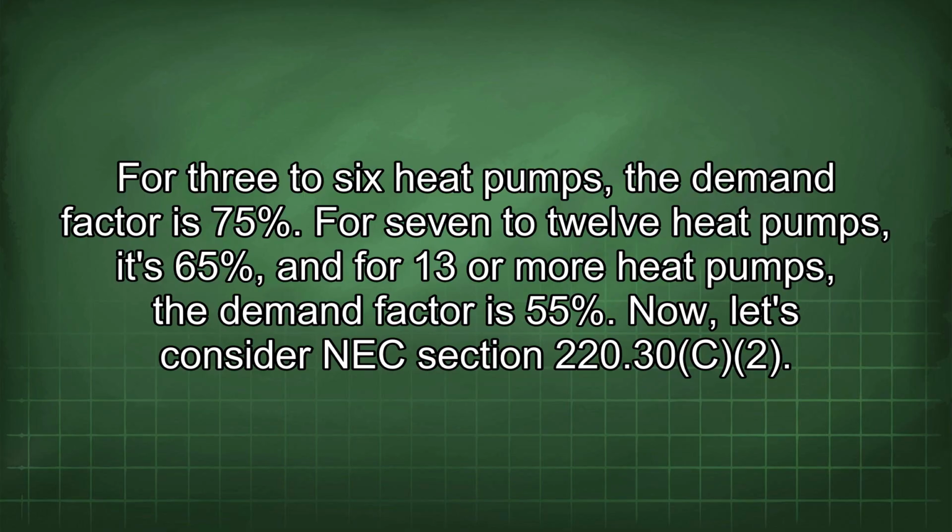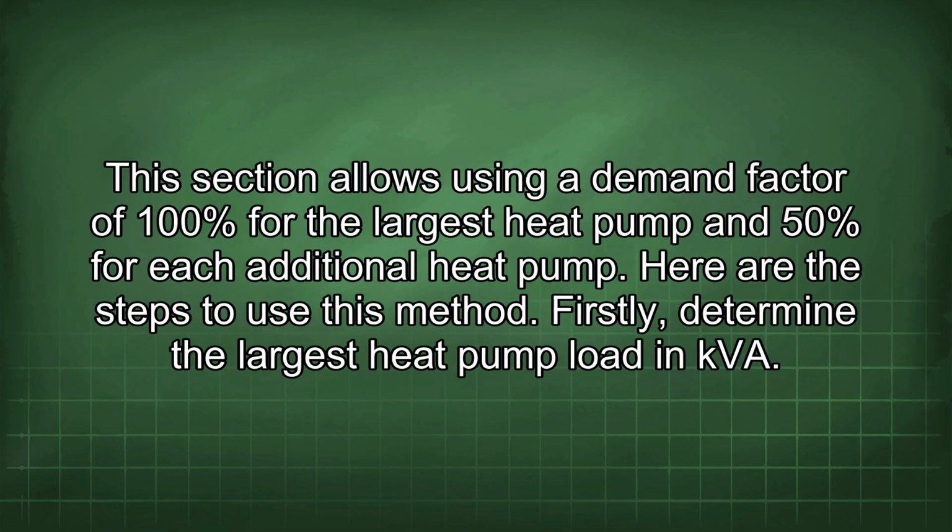Now let's consider NEC section 220.30C2. This section allows using a demand factor of 100% for the largest heat pump and 50% for each additional heat pump. Here are the steps to use this method.